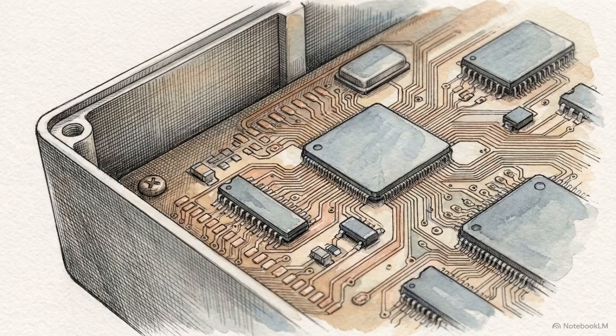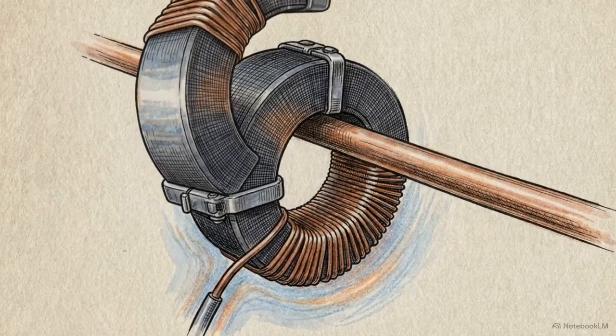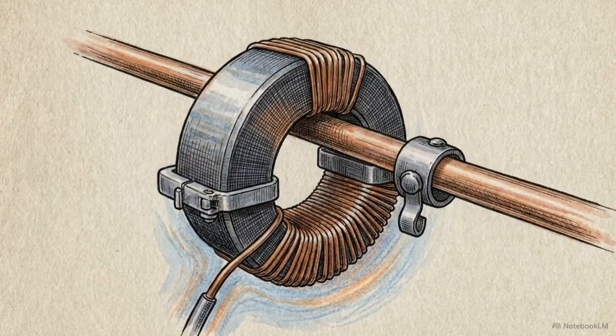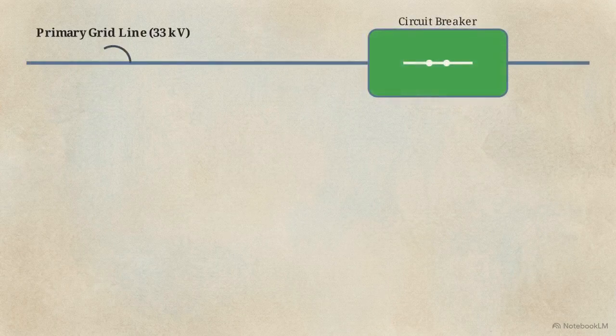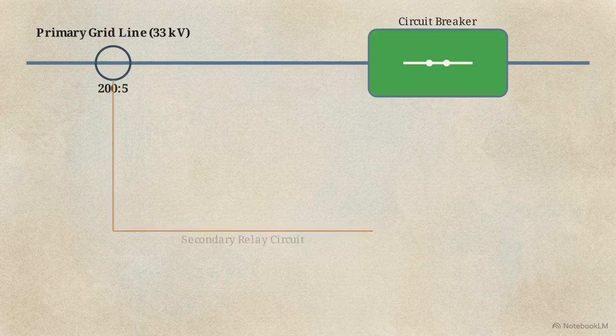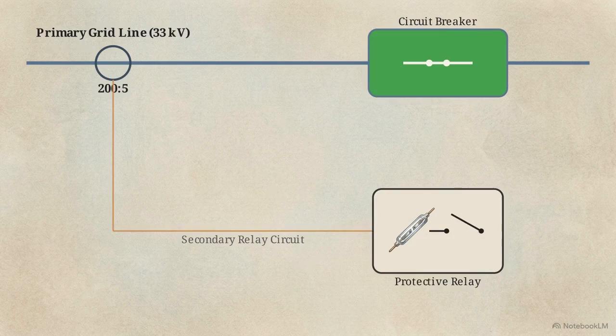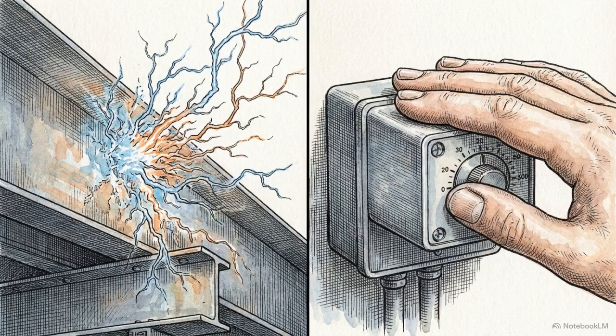The protective relay microprocessors sitting in the control room cannot physically handle 245 amps. We use a current transformer, or CT, clamped onto the line to magnetically step that power down to a safe proportional level. We apply a common CT ratio of 200 to 5 amps. This means for every 200 amps passing through the primary grid line, exactly 5 amps are sent to the relay. We take our 245 amp threshold, multiply it by 5, and divide by 200. The math gives us 6.125 amps. This tiny secondary current is the precise electrical value that will physically hit the relay and trigger the circuit breaker to trip. By utilizing precise proportional scaling, engineers translate massive, lethal primary grid forces into highly manageable secondary trigger values.